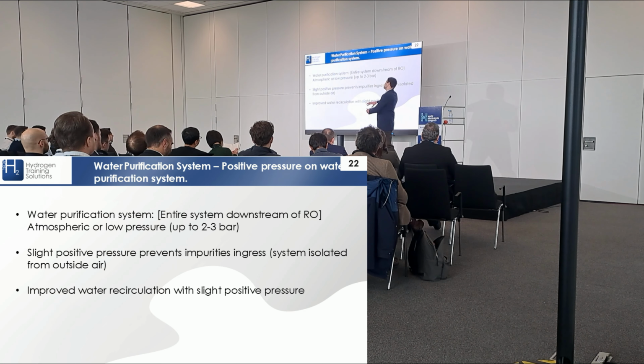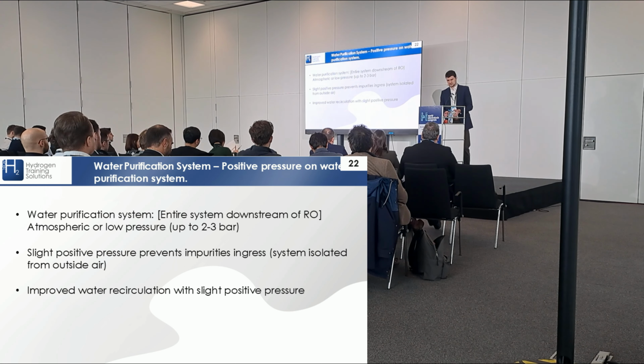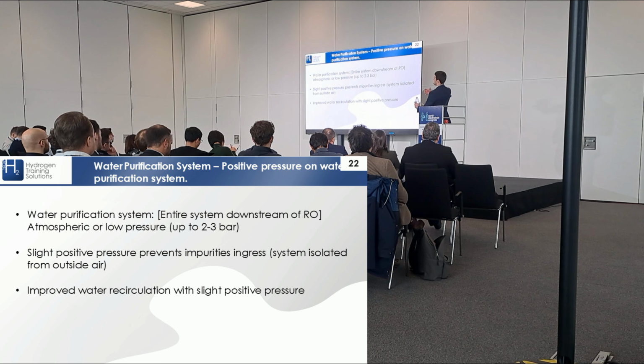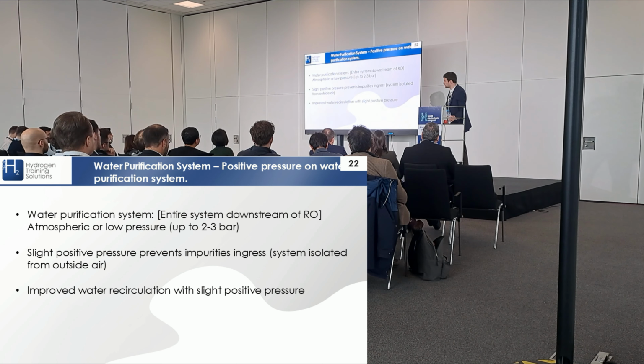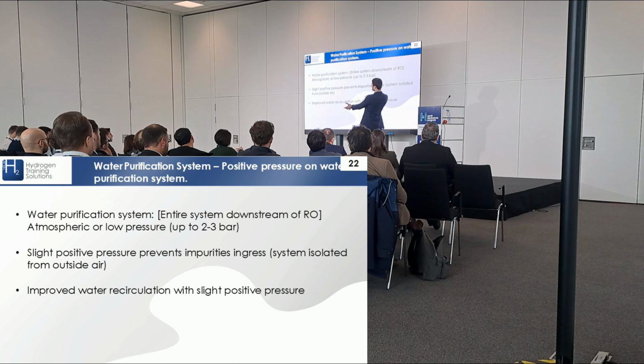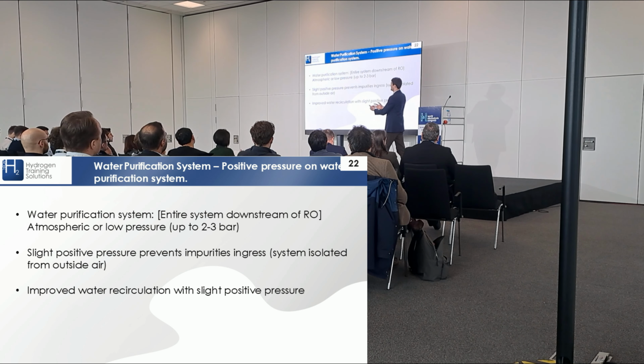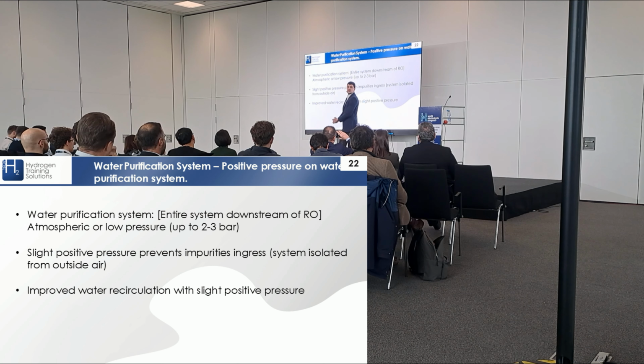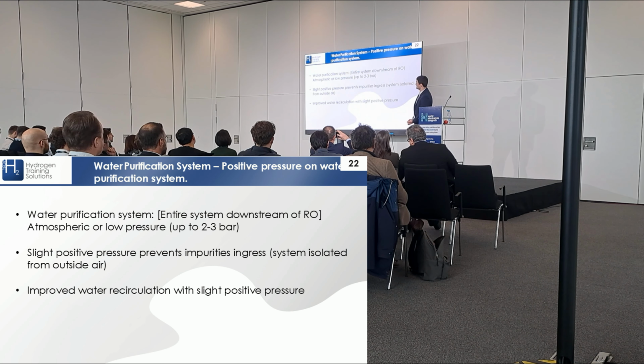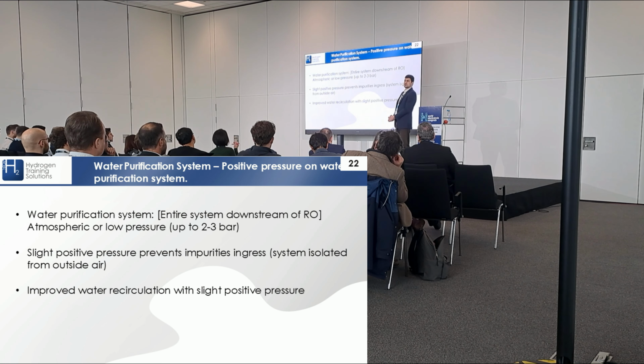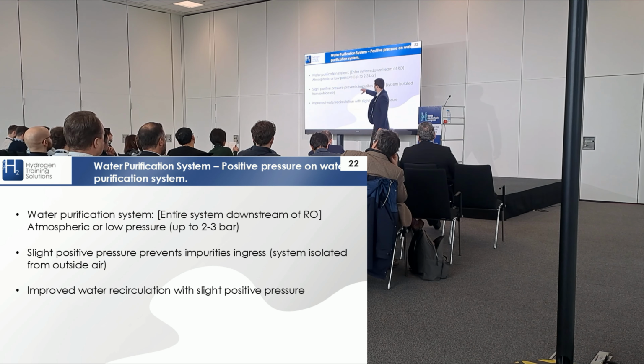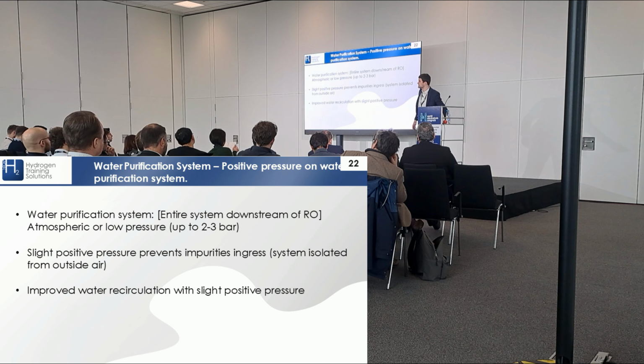This also comes under innovations, but I haven't put it there because some OEMs are already offering this. What we're talking about here is the water purification system pressure. Some systems are at atmospheric pressure, but other systems are at low pressure - not high pressure, but an ever so slight pressure, up to 2 or 3 bars. What this does is it prevents ingress of impurities.